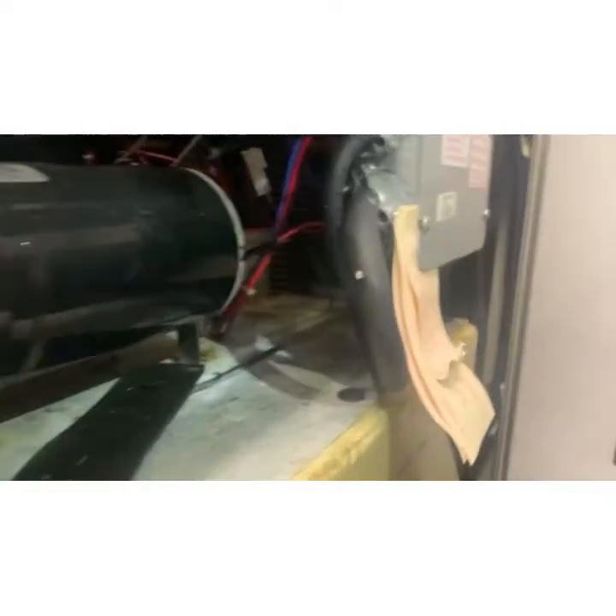Except this is all ice cold, so it's probably 38 degrees in this cabinet, which means we've got a bad temperature probe. We'll get in there later and show you. See that wire right there? That's the cabinet temp probe. We'll get that opened up and show you what we're talking about.